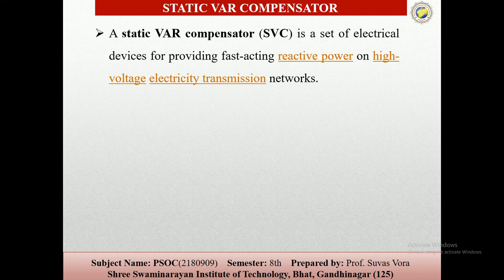As we already studied, the static VAR compensator is a set of electrical devices for providing fast-acting reactive power on high voltage electricity transmission networks. So these compensators provide fast reactive power to transmission networks, and this method makes the power system operate at unity power factor by automatically matching the impedance.